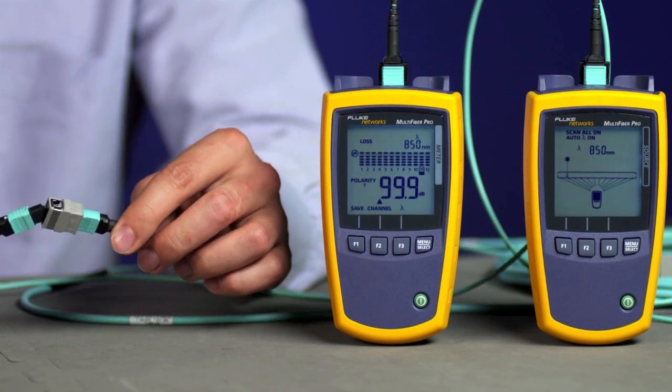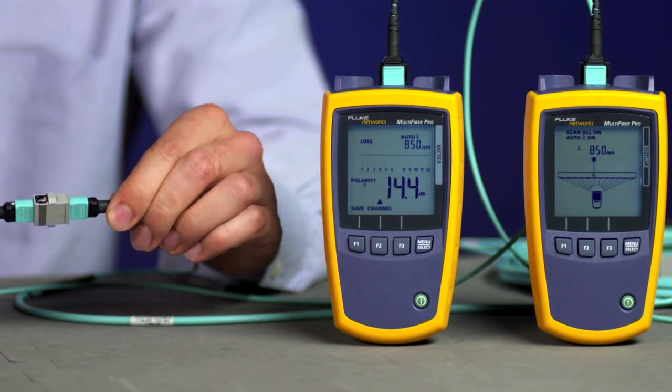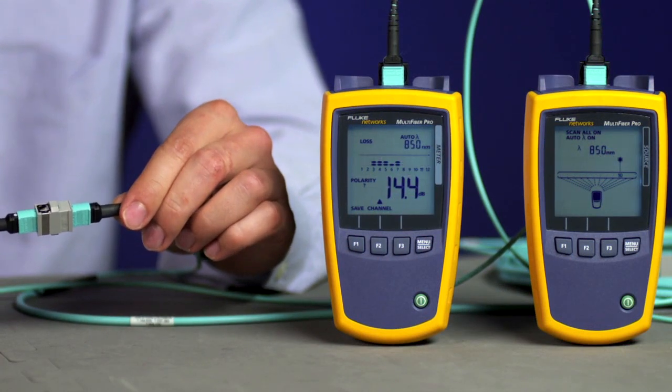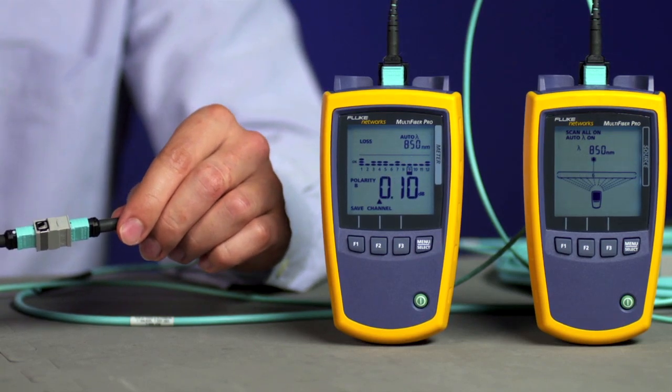Now simply connect your test cords to the MPO trunk cable, and in less than 6 seconds you'll have the loss and polarity measurements for all 12 fibers. The simple user interface allows you to easily determine if the cable passes the loss criteria you set. Any fiber that has excessive loss will be easy to spot in the simple bar graph.